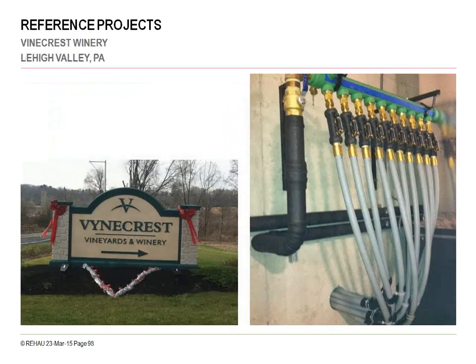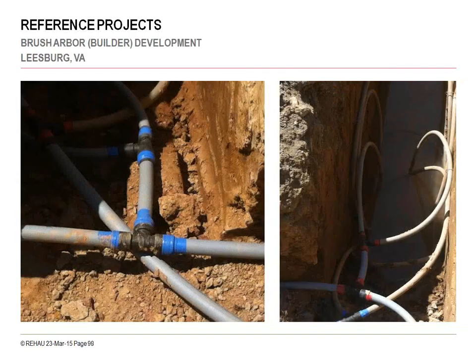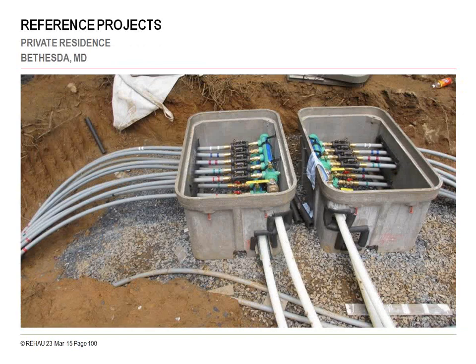This is a winery project in Pennsylvania. This is a new construction builder project. For some of the smaller jobs, instead of doing those larger precast vaults, you can have these quasi boxes, kind of utility box, and locate the balancing manifolds inside of there. And these can be closer to the borehole field outside as opposed to in the mechanical room. And then you would have, you can see here, your main supplies and return 2-inch supply and return coming off of the manifolds going into the mechanical room.